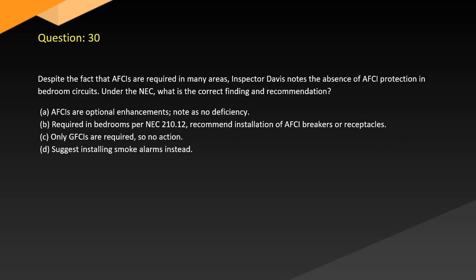Question 30. Despite the fact that AFCIs are required in many areas, the inspector notes the absence of AFCI protection in bedroom circuits. Under the NEC, what is the correct finding and recommendation? A. AFCIs are optional enhancements; note as no deficiency. B. Required in bedrooms per NEC 210.12. Recommend installation of AFCI breakers or receptacles. C. Only GFCIs are required, so no action. D. Suggest installing smoke alarms instead.